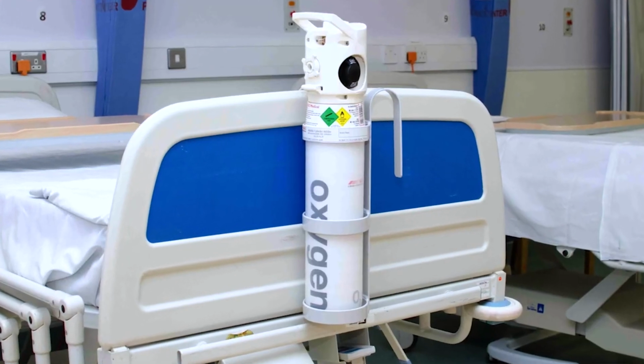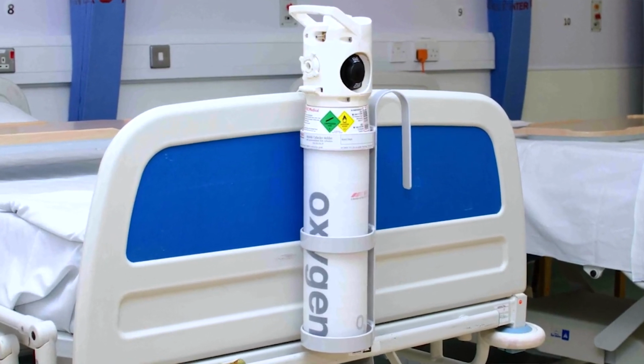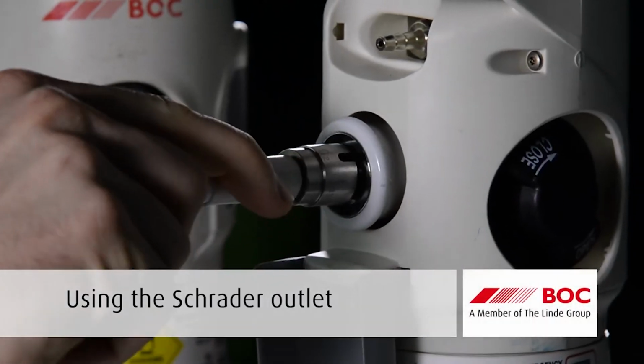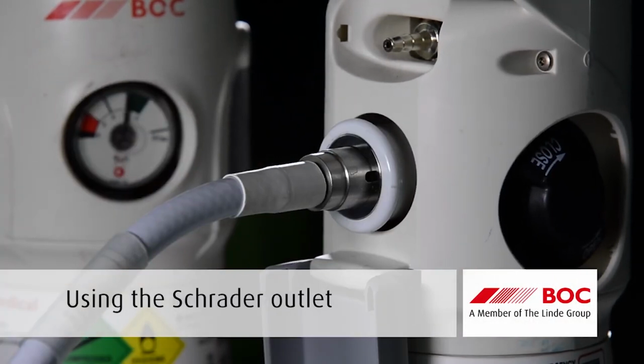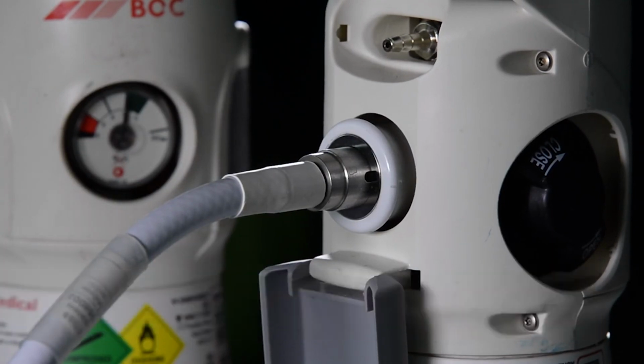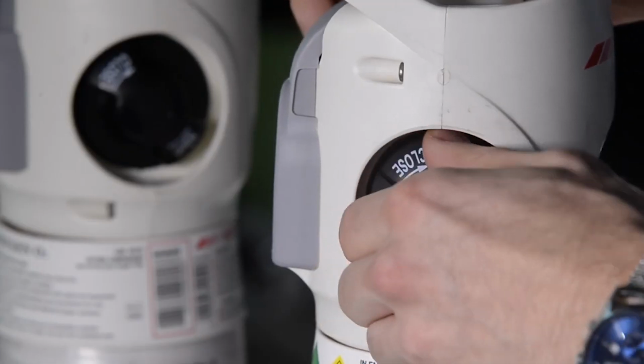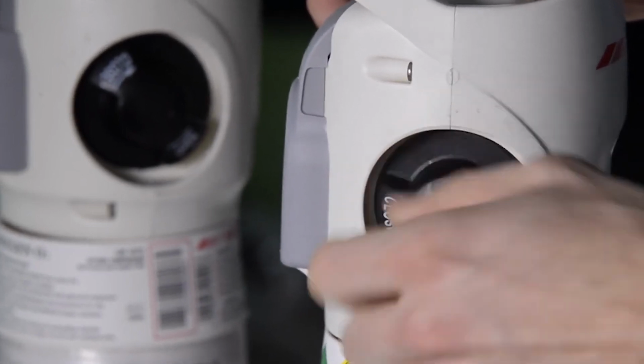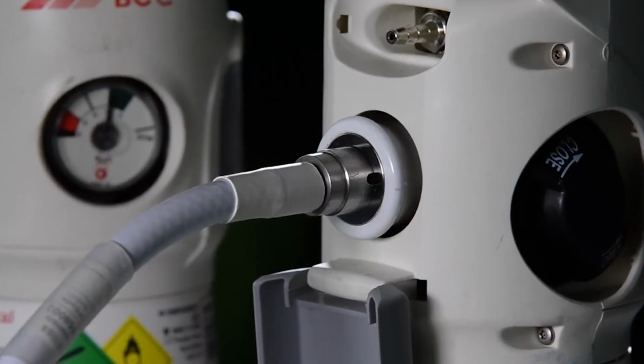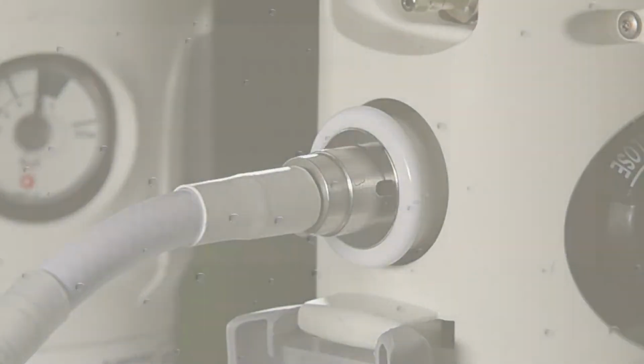Use a suitable cylinder holder where possible. Insert the oxygen probe into the Schrader outlet. Ensure the probe clicks securely into place. Slowly turn on the cylinder by rotating the hand wheel anti-clockwise until it comes to a stop. Check for leaks, which may be indicated by a hissing sound.